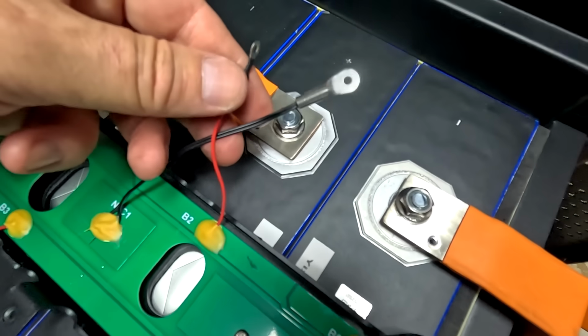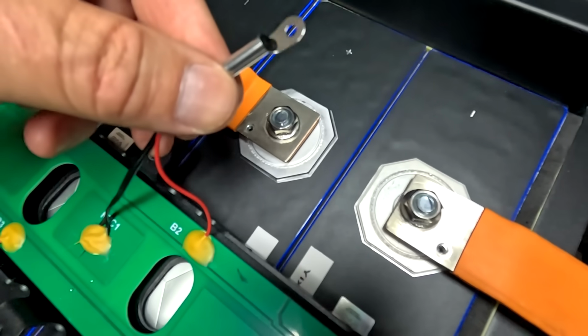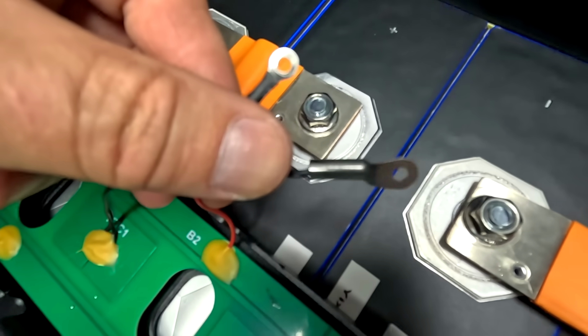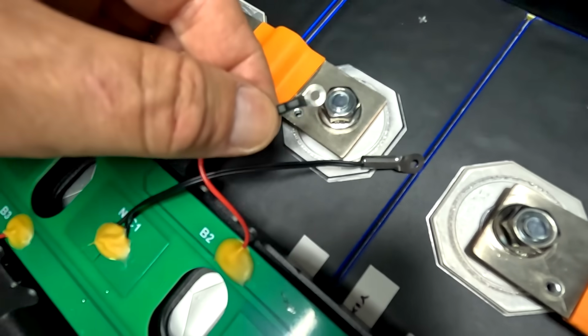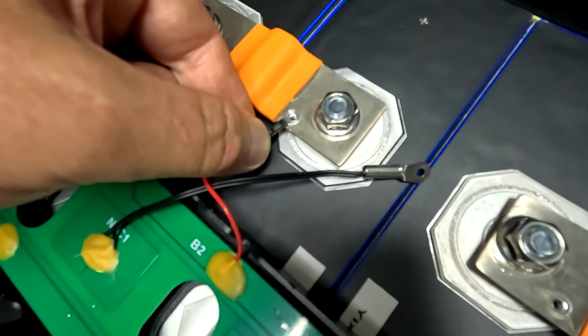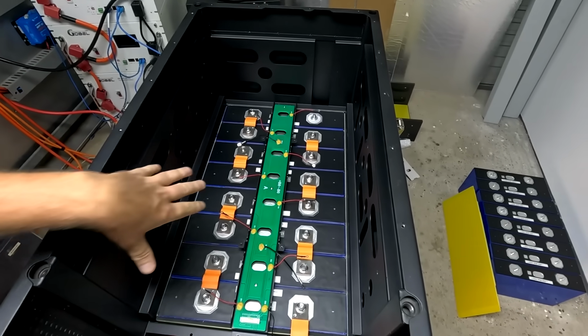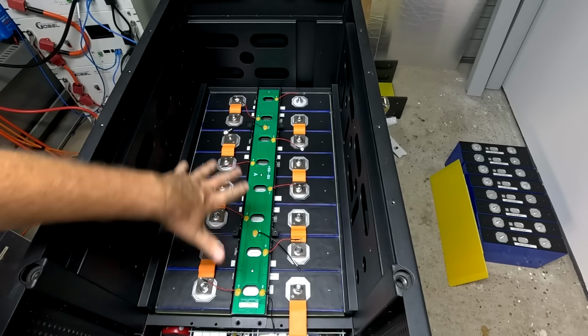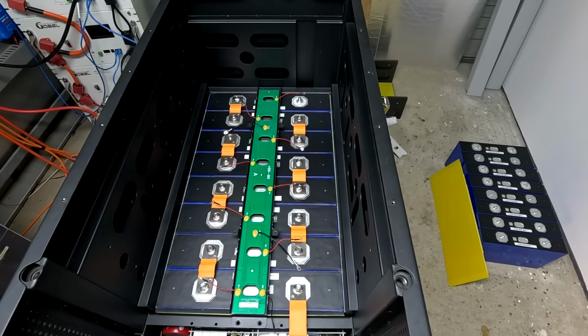See, all the balance cables and also the temperature sensors, they have small M3 ring lugs. They go directly here on the bus bar. So, because we have already mounted the bus bars now, we have created a 24-volt battery, and we probably want to start isolating the terminals now.